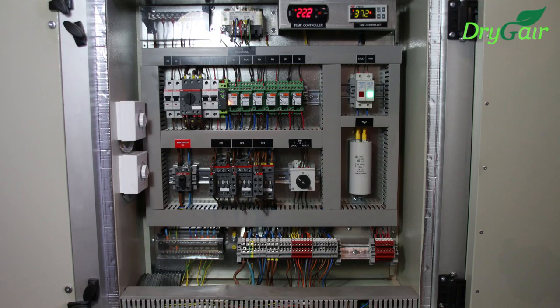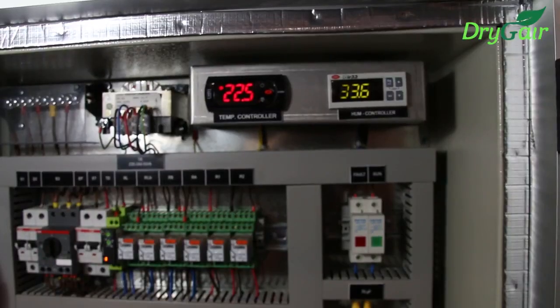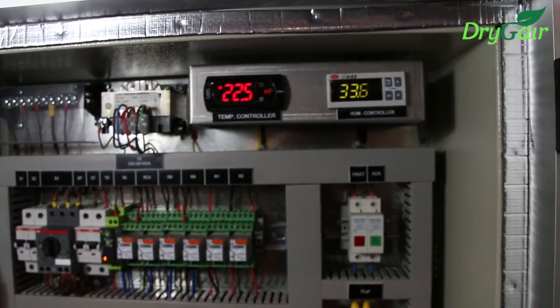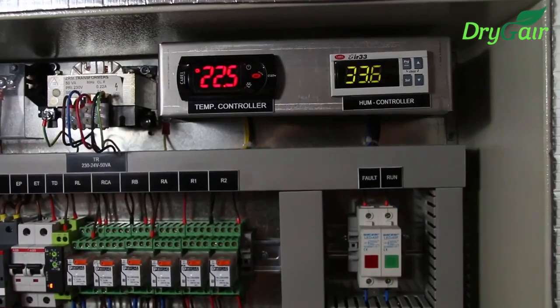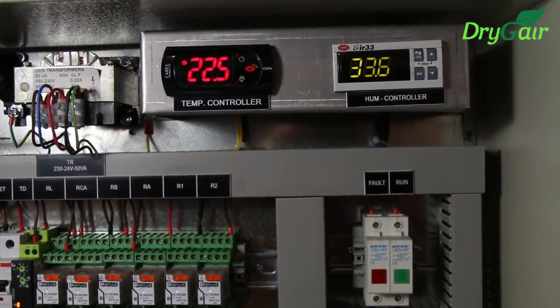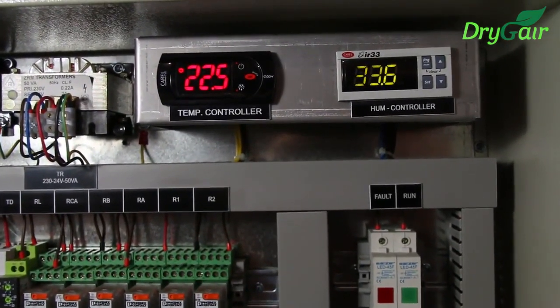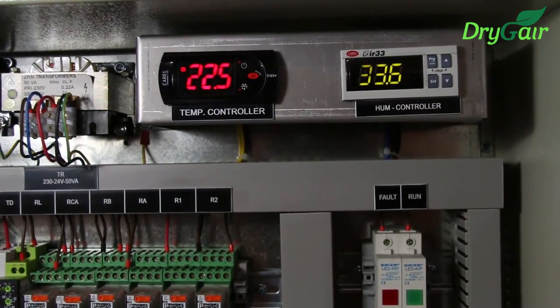Now we will set the desired relative humidity percentage, or set point, into the humidity controller. If you look at the display, you will see that the humidistat on the right shows the current relative humidity level that the sensor reads, 33.6%.